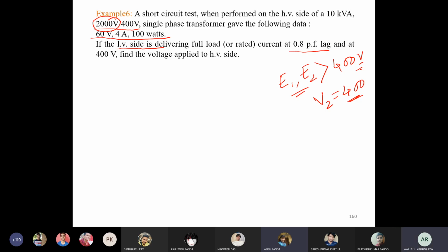So how to find that? We can find that by calculating the change in terminal voltage. So for that we need RE2 and XE2, that we can calculate from the short circuit test data. Once we get this, we will be able to calculate E2 minus V2. We know this from the voltage regulation calculation.